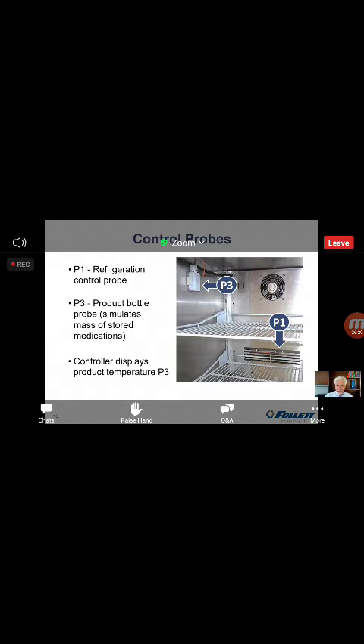Now, P2, we didn't neglect that one, didn't forget about that. That's only on freezers. Your P2 probe, and it's not in sight here, but we are going to look at it in just a few minutes. That is embedded into the fin block of the evaporator coil itself. It monitors the temperature of the evaporator coil, and we use that for terminating the defrost cycle. We don't want the units to be in the defrost cycle any longer than they have to be, and that's why we monitor that temperature, because of course when you're defrosting the unit, you can't be providing and delivering cooling to the product.